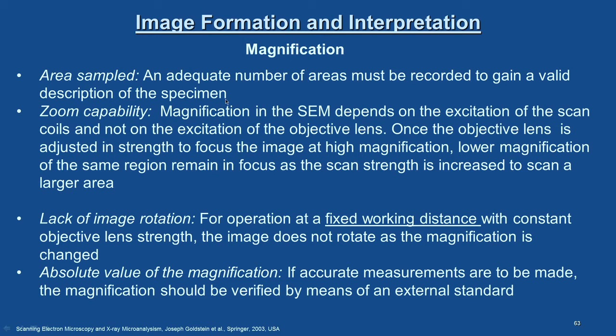Only by examining an adequate number of areas can you say that you have imaged the specimen with a reasonable representation of bulk information. Collecting only very high magnification images in one or two locations may not represent the bulk information. Regarding zoom capability: magnification in SEM depends on the excitation of the scan coils, not the objective lens. Once the objective lens is focused at high magnification, low magnification of the same region remains in focus as the scan area is increased.